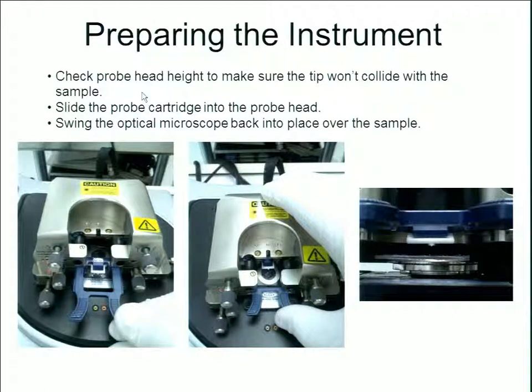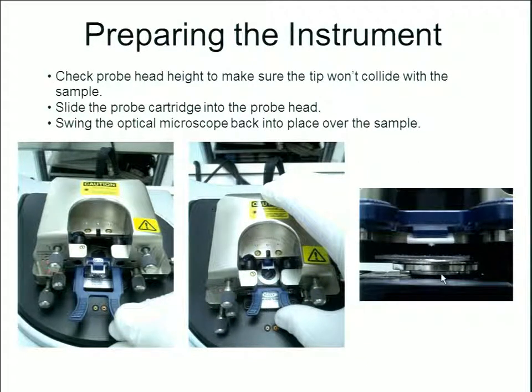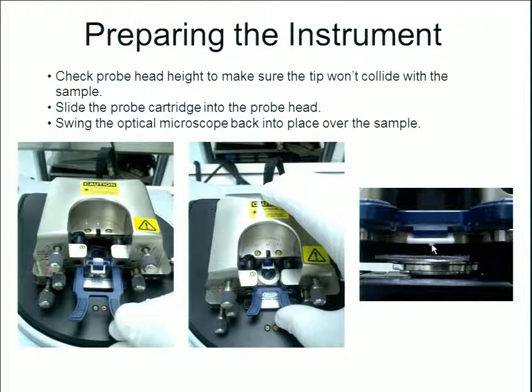To prepare the instrument, check the probe head to make sure there won't be any collision, then carefully slide the probe cartridge into the probe head. Swing the optical microscope back into place — it will look down at the cantilever to help with laser alignment. From a side view we can see: the piezoelectric, the magnetic plate, the magnetic disc with the sample, the cantilever, the chip, the chip carrier, and the probe cartridge, all inside the probe head.